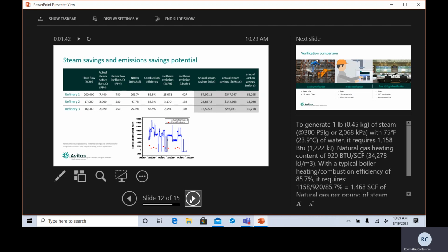By going from 85.5% combustion efficiency to 98, not only are you compliant, but you're also saving, in metric tons, 62,000 metric tons per year. Average carbon tax in Canada, I think, is at $20 per metric ton. I think in Europe it's around the same. If that were to be put in place in the US, $1.2 million savings right there. So we need to prepare for the future. We all know that this sort of thing is coming. So now is the time to not just be compliant with RSR, but to move forward and get ready for, by 2030, when there's various taxes.